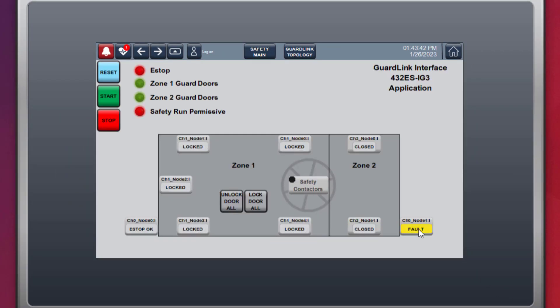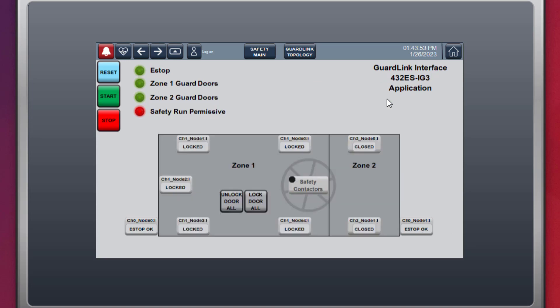To fix the discrepancy fault, replace the wire on channel B. Cycle the emergency stop push button. The device becomes run ready. Press the machine reset and start. The machine returns to operation.